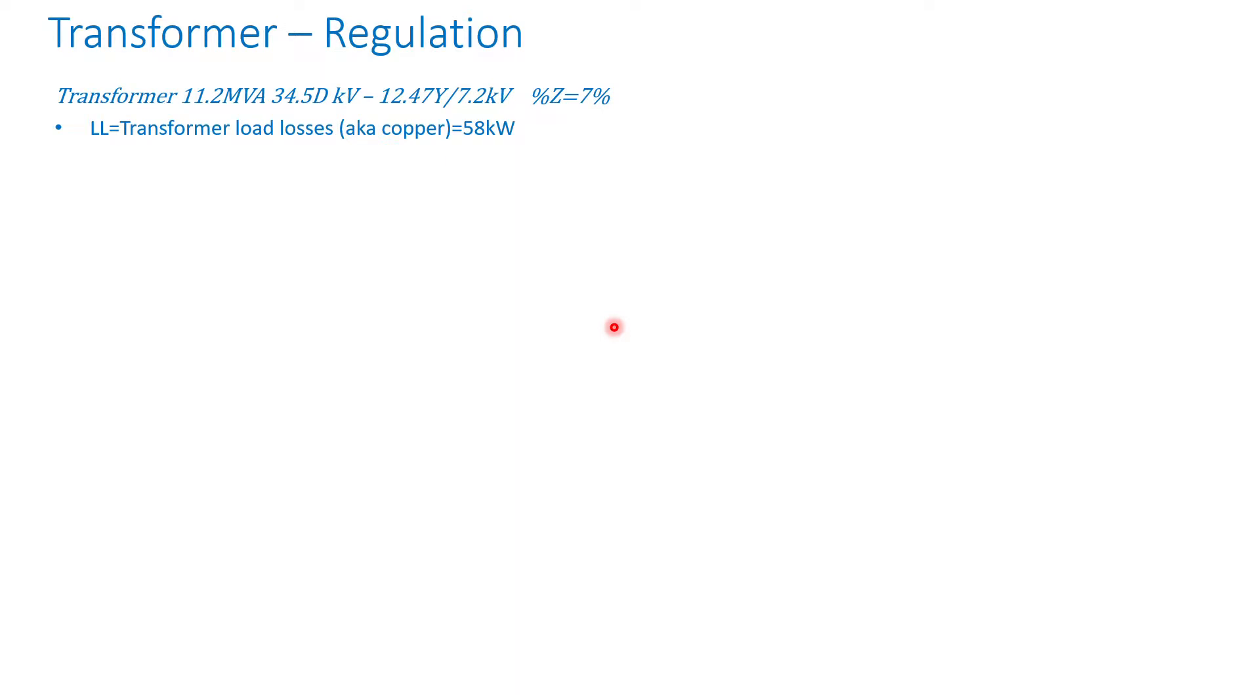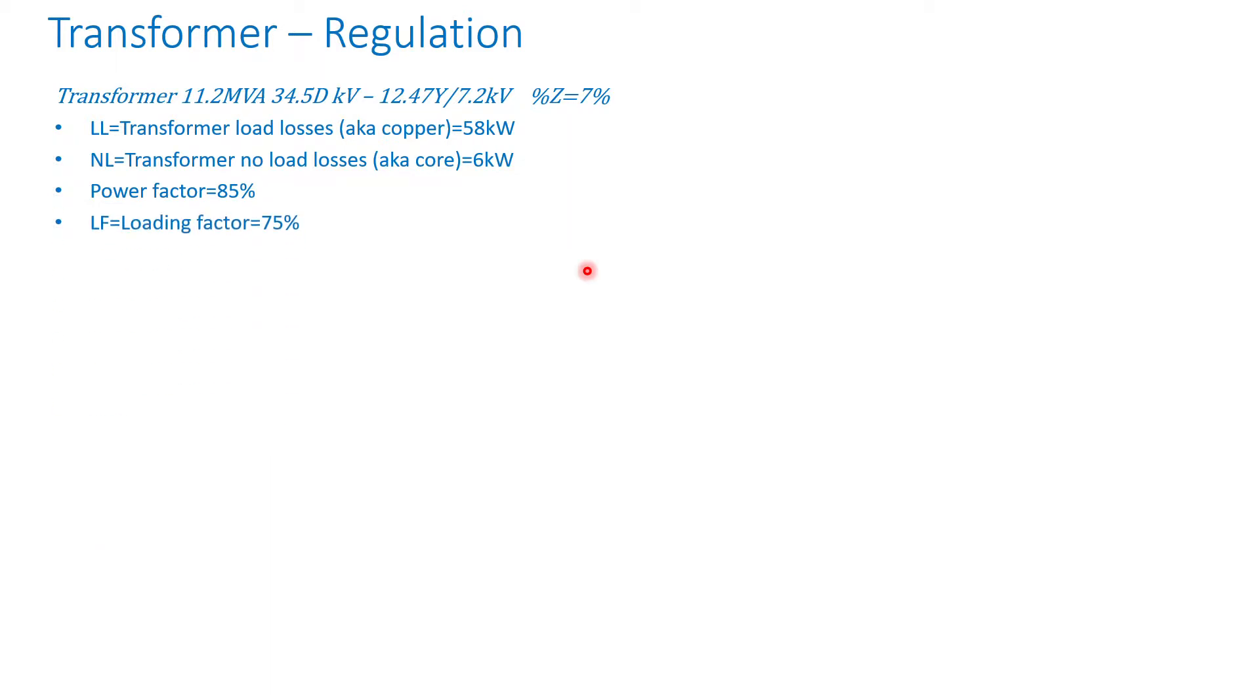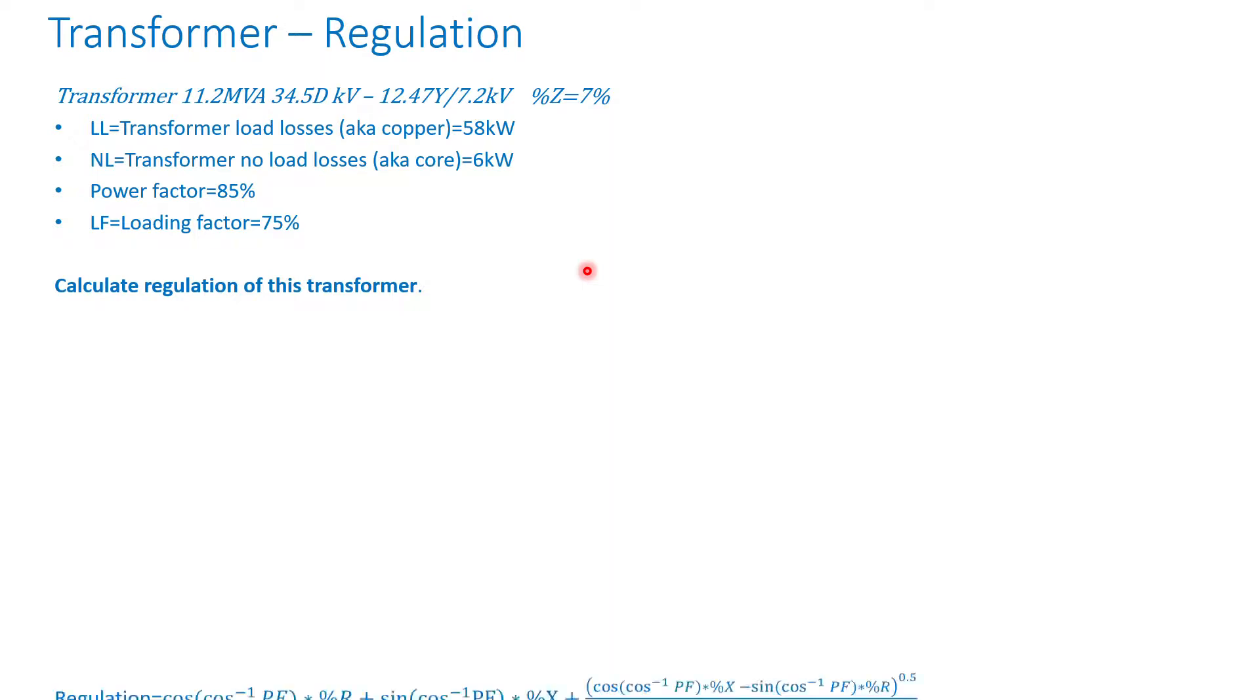Let's assume we have a transformer rated 11.2 MVA, 34.5 kV delta, 12.47 kV with an impedance of 7%, load loss 58 kilowatts, and core loss is 6 kilowatts. Power factor is 85%, loading factor is 75%, and we want to calculate regulation of this transformer.